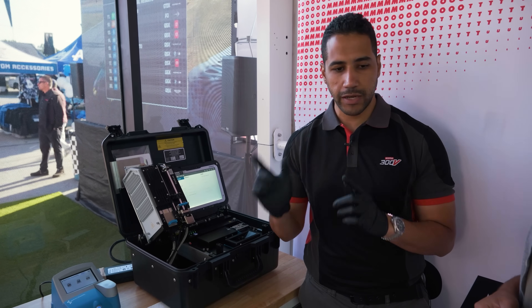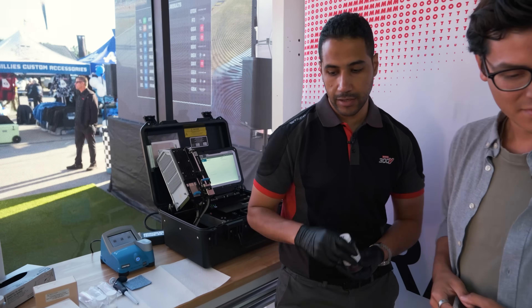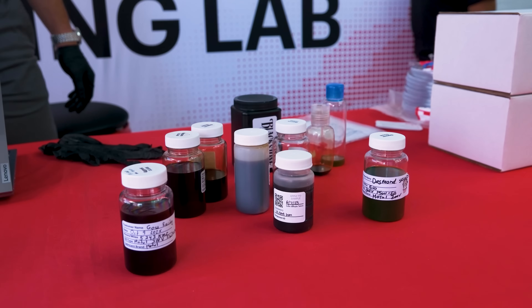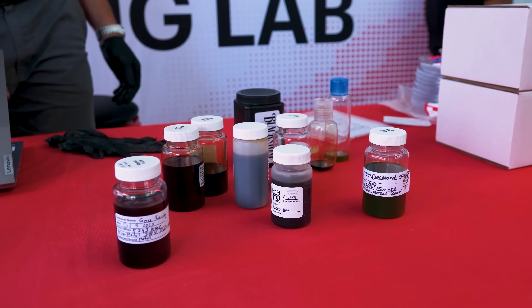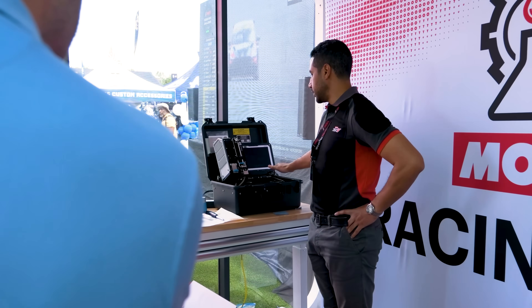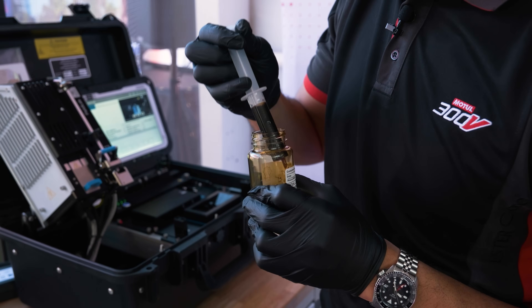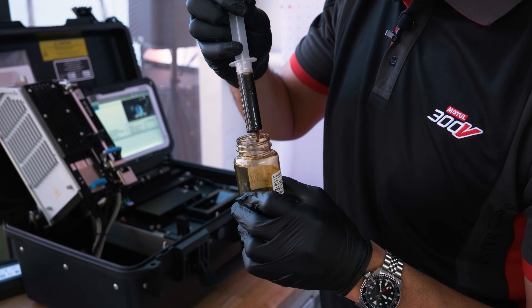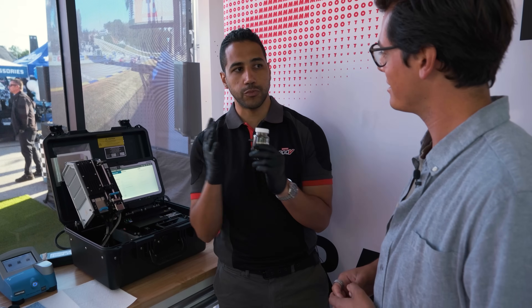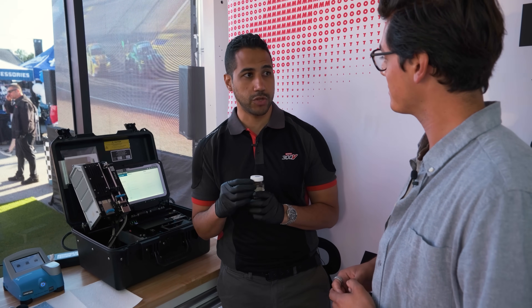We provide the teams with empty bottles — they fill them in with a sample. You can see just a few milliliters, but you can tell a story about what's going on — not just about the oil, but more importantly about the equipment itself. Starting with viscosity: viscosity is the most important property of the oil, the first line of defense. If the viscosity is in proper shape, it will protect the engine parts, prevent metal contact, and reduce wear as much as possible.